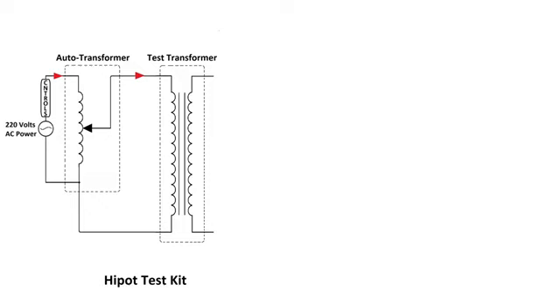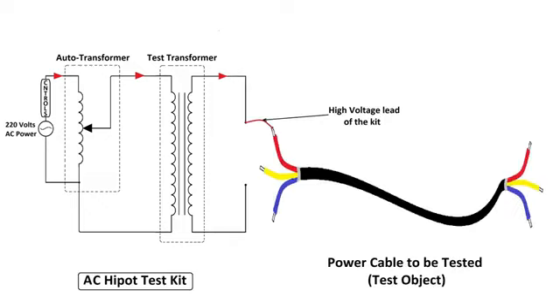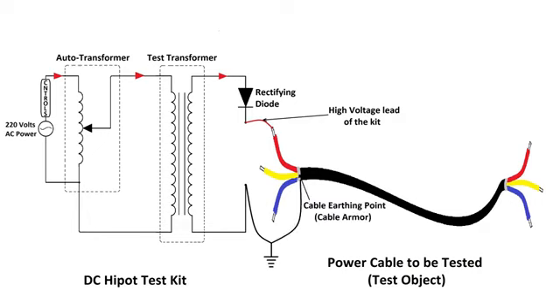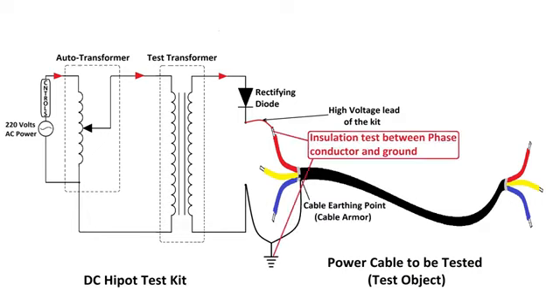In the case of AC hipot testing, the secondary winding terminal of the test transformer is connected to the phase conductor of the cable. In the case of DC hipot testing, a silicon rectifying diode is connected in series with the secondary of the test transformer. The secondary terminal of the test transformer is connected to the phase conductor of the cable through this diode. And another terminal of the secondary of the test transformer is connected to the ground along with the cable armor. With this connection, insulation between the phase conductor and the ground is tested.